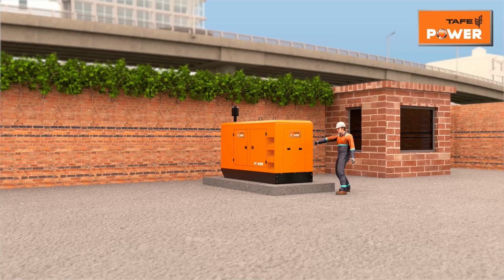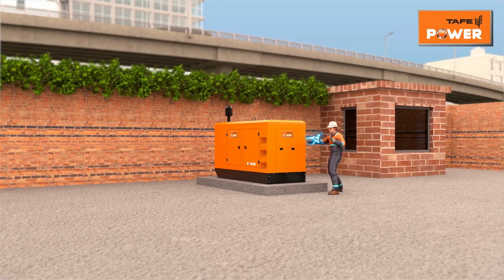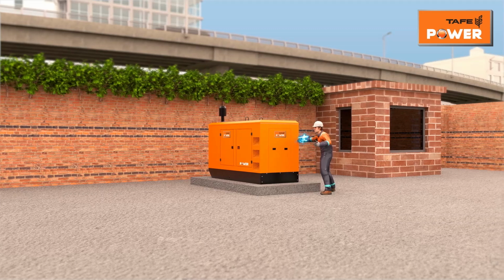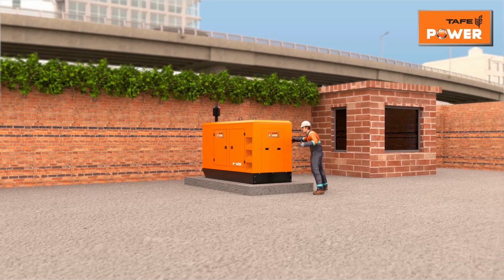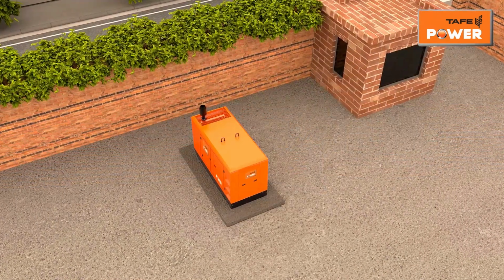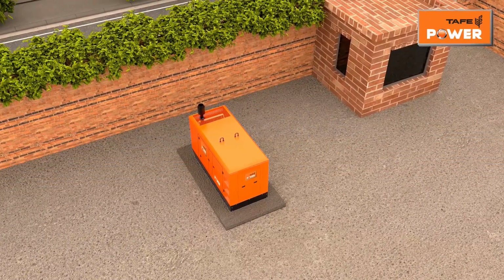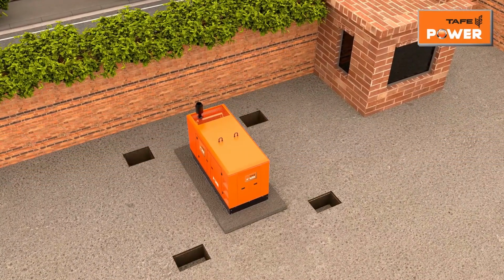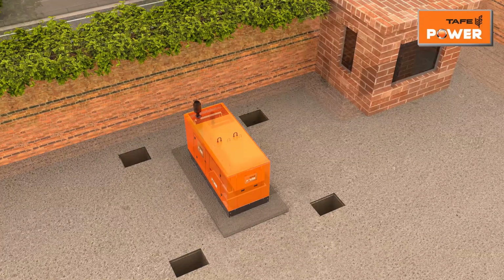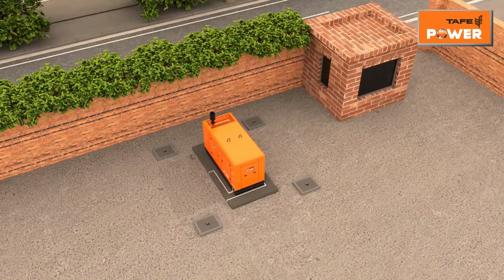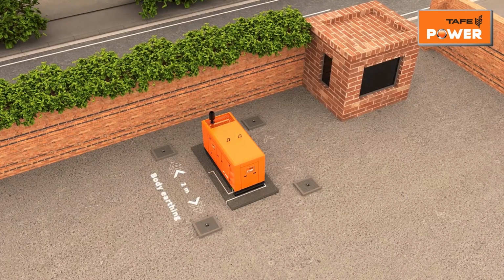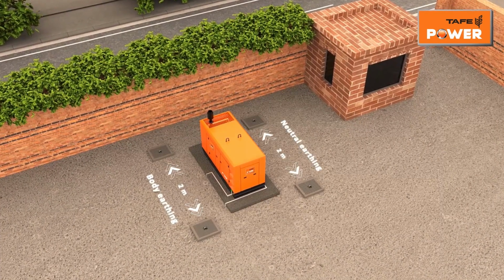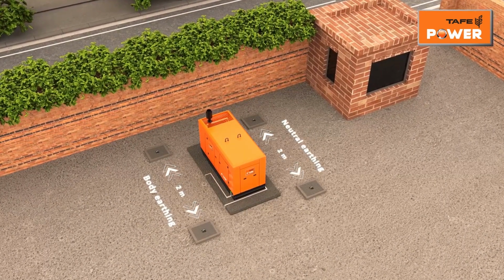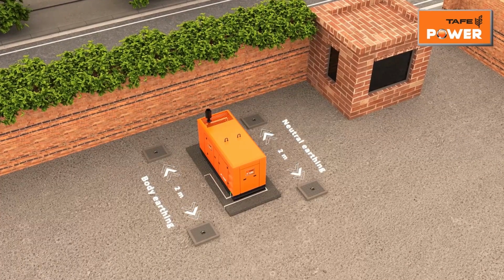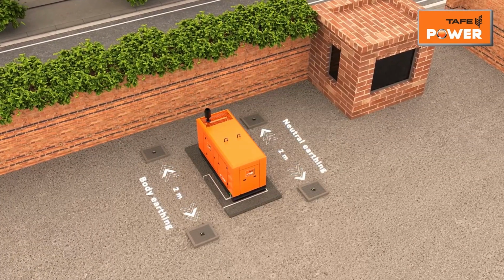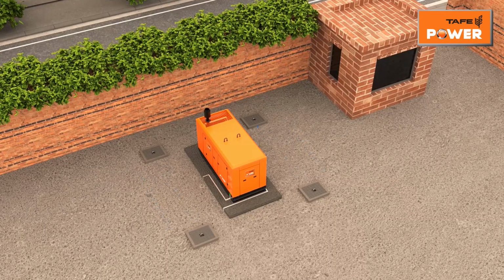Earthing. Earthing of alternator, neutral and genset body plays a vital role for grounding of fault current and is crucial for safety of operator and equipment. Commonly used earthing type are of copper plate earthing or chemical earthing. 4 earth pits are required for genset earthing, 2 numbers for body and 2 numbers for neutral earthing. Distance between 2 earth pits should be minimum 2 meters. The neutral earth pits and body earth pits should be located on opposite sides of the canopy.